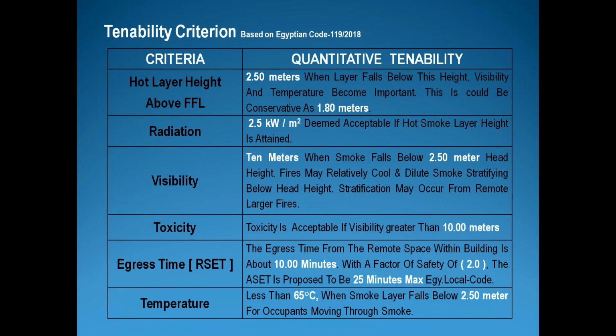For example, if you state that the evacuation will follow this corridor, you can imagine that the smoke will move in this corridor, so you can calculate the projected area of this corridor, and divide the average heat coming by radiation. Then you can use the normal radiation equation on the head of the people, considering that the head is at 32 or 36 degrees Celsius, the normal temperature of the human body. Then the visibility, 10 meters.